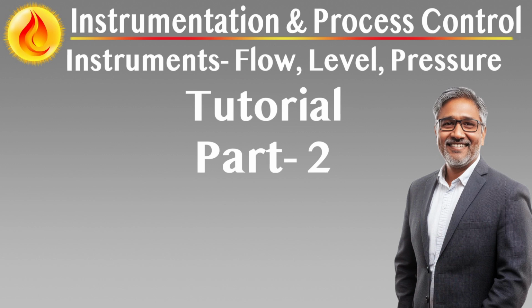Special requirements apply for instruments handling toxic fluids, high-pressure hydrocarbons, or corrosive agents. Their layout must minimize personnel exposure during maintenance, include clear labeling, venting, and isolation facilities, avoid installation near walkways or escape routes without protective shielding. While modern transmitters offer remote diagnostics and extended calibration intervals, that does not negate the need for strategic placement. Every instrument should be both operationally accurate and physically maintainable, a design standard that must be enforced, not assumed.